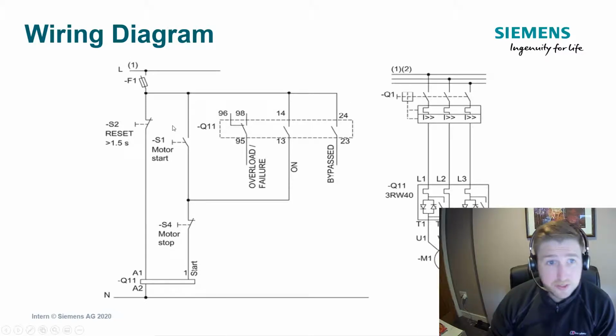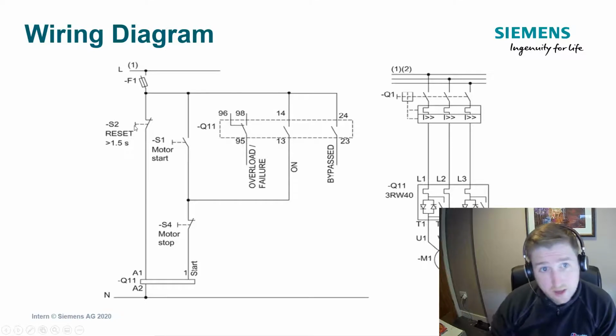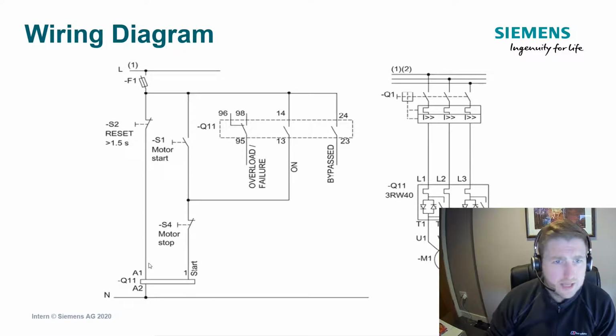If you hold a push button in for 1.5 seconds, that will automatically reset the soft starter for you as well. And it's as easy as that to connect the device and get it up and running in terms of the control circuit.